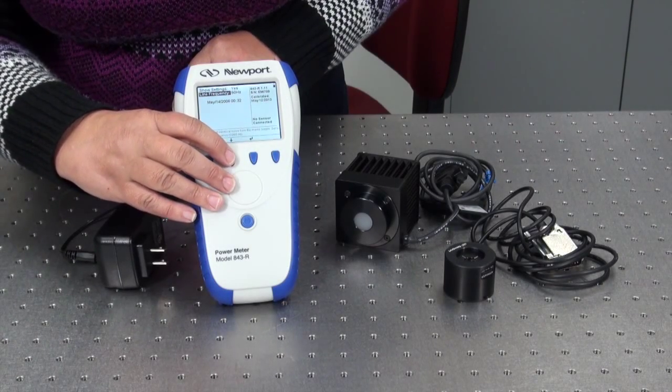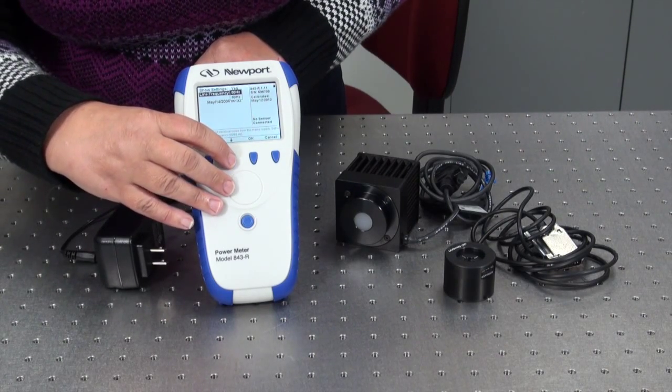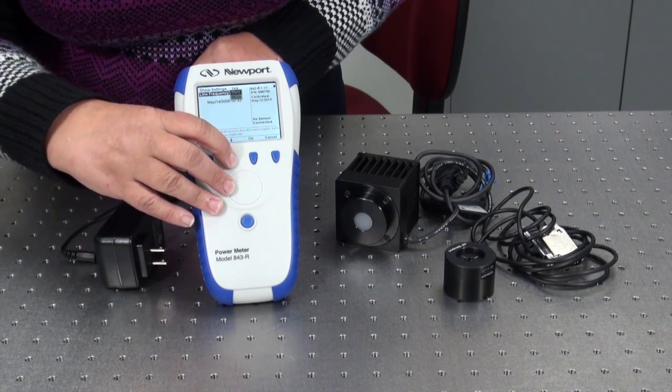Next, choose a setting for the line voltage frequency, either 50 or 60 hertz. Choosing the correct setting removes electrical noise that may be introduced into the system, thereby increasing the accuracy of the measurements. Press the down arrow until the line frequency is highlighted. Press the enter arrow. Select the correct line voltage for your power grid.